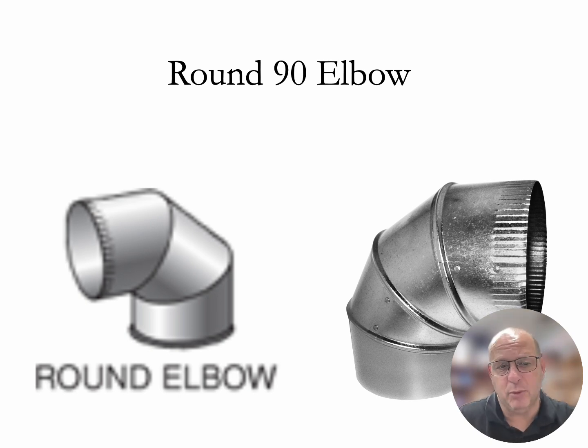The same principle goes into the securing of these pipes as the round pipes are. We want to put 3 screw holes in there, put one there in our sheet metal, and put one on top. And then we want to mastic every portion of the air that's coming through there.